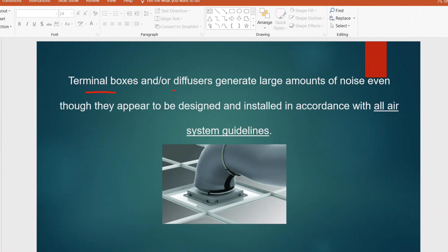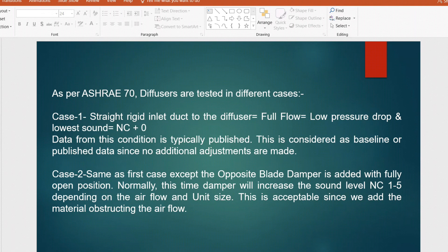The next question: VAV terminal boxes and diffusers generate a large amount of noise even when they appear to be designed and installed in accordance with all air system guidelines. As per ASHRAE 70, diffusers are tested in different cases. Case 1 is a straight rigid inlet duct to the diffuser with full flow and no flexible duct — resulting in low pressure drop and lowest sound. The data from this condition is normally published in the technical data sheet.